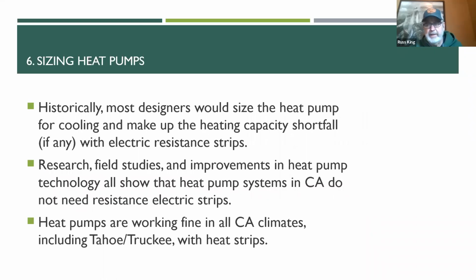Now, historically, the way they did it is they would just calculate the heating load and the cooling load, and they would size the heat pump to the cooling load to make sure that the house cooled properly. And if it wasn't big enough for heating, they would just throw some resistance electric strips on there to make up the difference. Well, we don't want that anymore. Electric resistance strips use too much energy, too much electricity. And so we've changed the way we size heat pumps over the years. So research, field studies, and improvements in heat pump technology itself all show that we no longer need heat strips in California. Heat pumps are working fine in all climates in California, even Tahoe and Truckee. There's heat pumps up there with no heat strips that are working just fine.